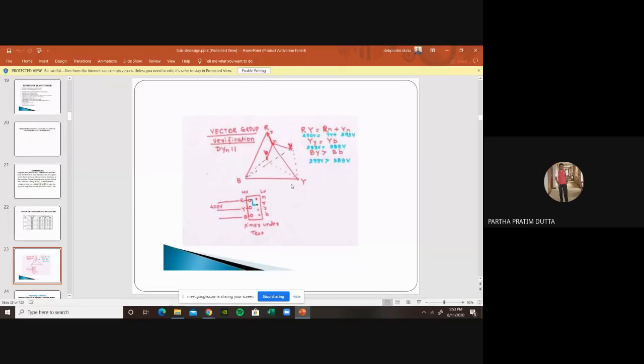And then comes the TTR, or transformer turns ratio. So usually all these three tests, core balance, transformer turns ratio test, I mean voltage ratio test later on, and the vector group test, are usually done through an instrument called the TTR instrument, and the turns ratio you see everywhere. I have told you the 33 kV by 11 kV by 3 root 3.